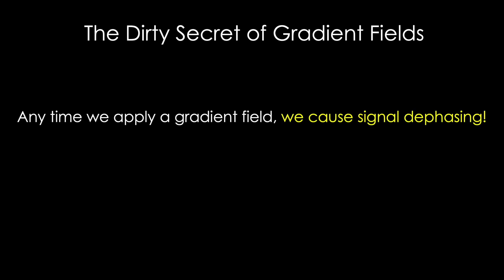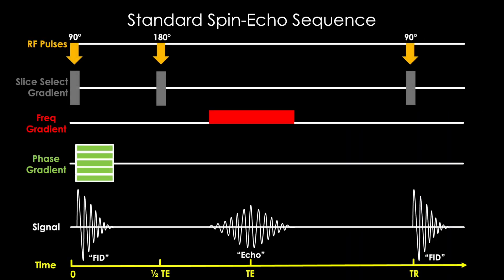So this brings us to the dirty secret of gradient fields that no one talks about. Any time we apply a gradient field, we cause signal dephasing. And the stronger the applied gradient field and longer it's applied, the greater degree of dephasing that occurs. So going back to the standard spin echo sequence, when we apply a phase encoding gradient, we decrease the signal. When we apply our frequency encoding gradient, guess what happens? We decrease our signal.